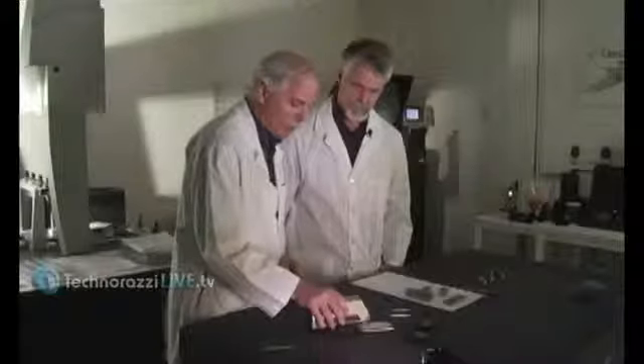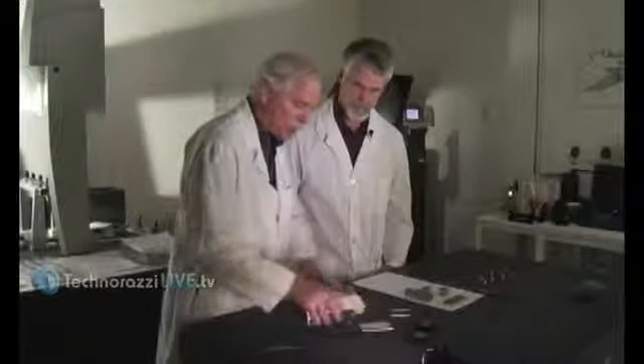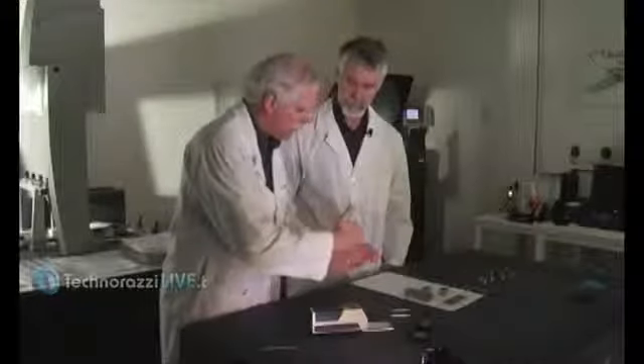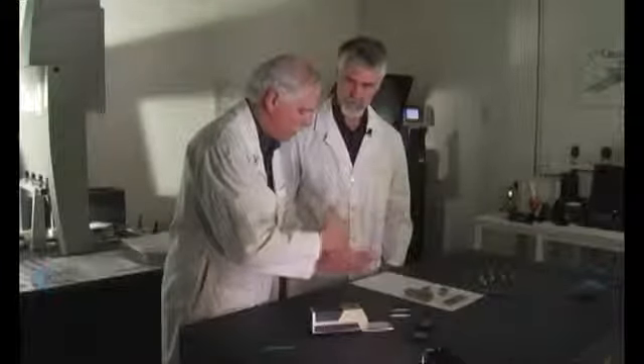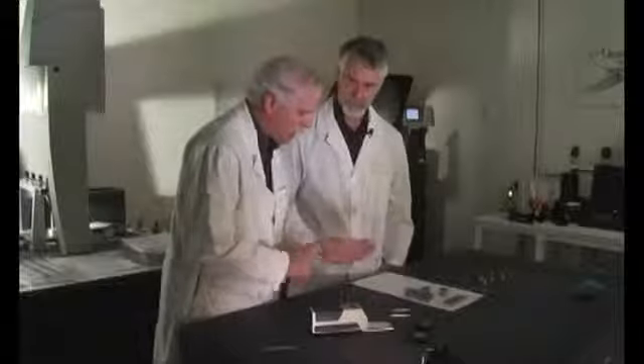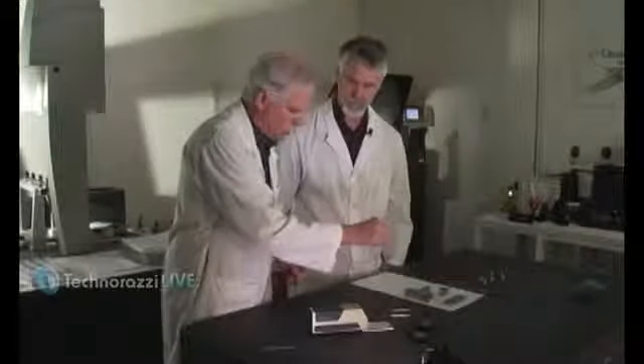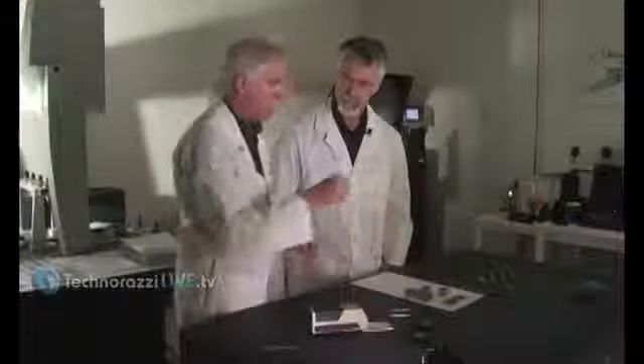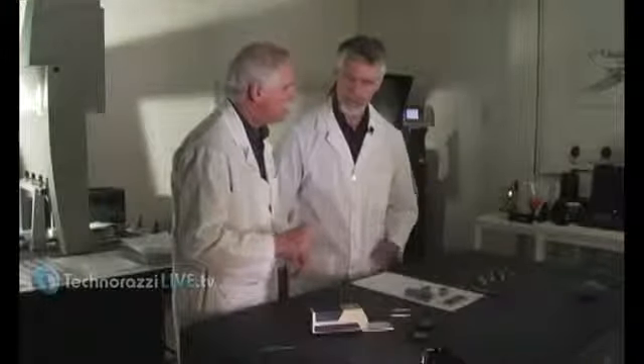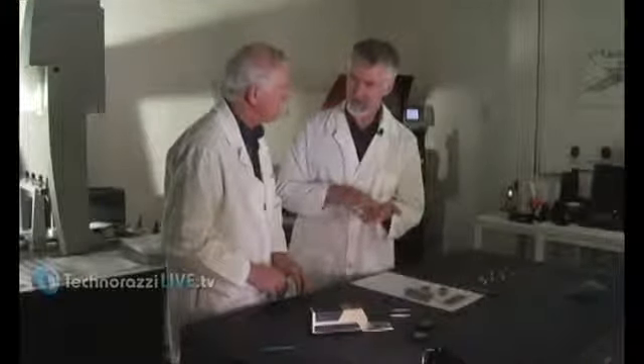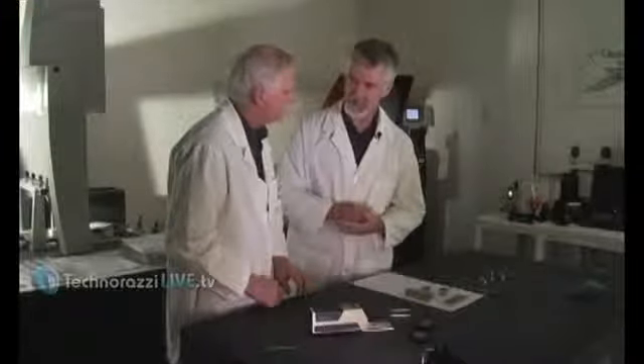Setup on these is very important. Being portable, a lot of times the tendency might just be to set it down, take a number and go. This stylus travels in and out. It has to be perpendicular to the lay of the roughness. If it's not, that tracer is still going to hit the top of the mountains, but it's not going to go all the way down to the valley. It's going to start up the next mountain before it gets there. So you actually have to know kind of the grain, so to speak, of the surface that you're measuring.